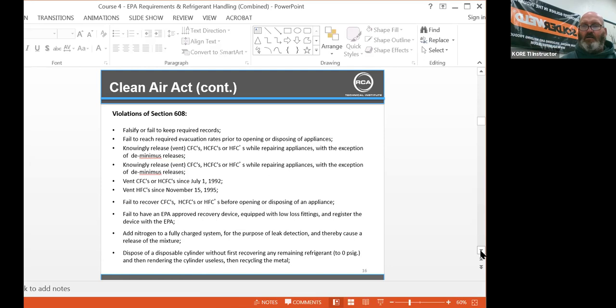Ductless split systems, VRFs and VRVs used to come with a static charge on the condenser. We would hook up the liquid line, vent refrigerant all the way through the line, come back through the suction side and let it bleed out, put a little bit of oil on it, hook it right up, tighten the flare, and call it good. We knowingly did that for years on Mitsubishi Mr. Slims and ductless splits in the early 90s. That's what they're talking about there.